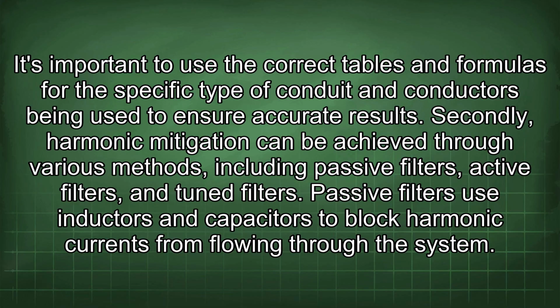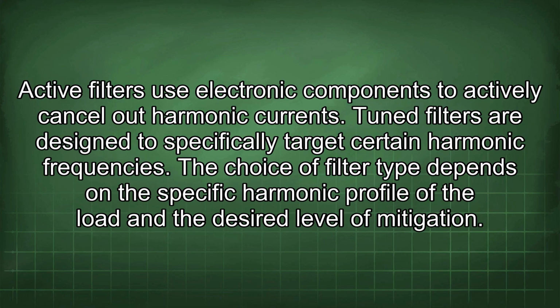Secondly, harmonic mitigation can be achieved through various methods, including passive filters, active filters, and tuned filters. Passive filters use inductors and capacitors to block harmonic currents from flowing through the system. Active filters use electronic components to actively cancel out harmonic currents. Tuned filters are designed to specifically target certain harmonic frequencies. The choice of filter type depends on the specific harmonic profile of the load and the desired level of mitigation.